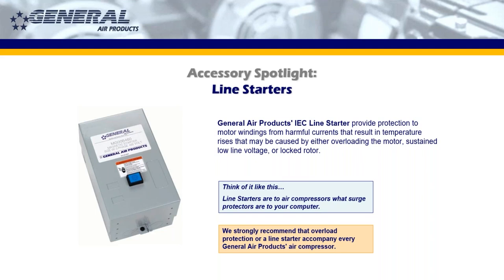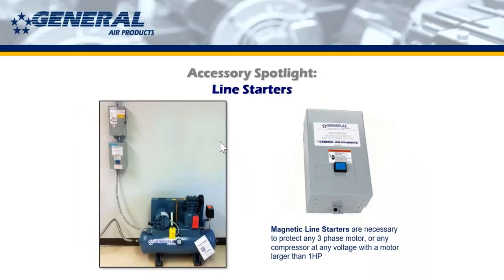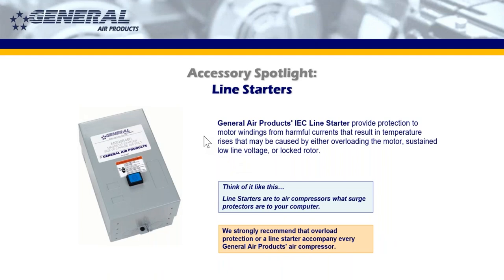Line starters. They're called magnetic line starters, motor starters, magnetic starters, all sorts of things. I think it's a terrible name because they more stop things than start them. First, to explain what these line starters are, you'll see them on three-phase units typically. It's a fundamental requirement of a three-phase motor to have a line starter on it and have protection like that. So when you're wiring a three-phase motor, there are lines already there that will allow the motor to run, but it's necessary to put in the line starter in order to do that.